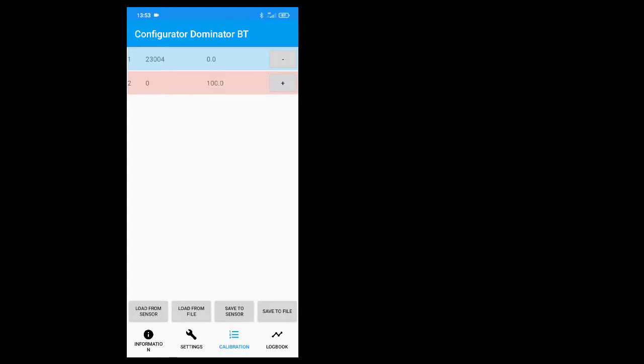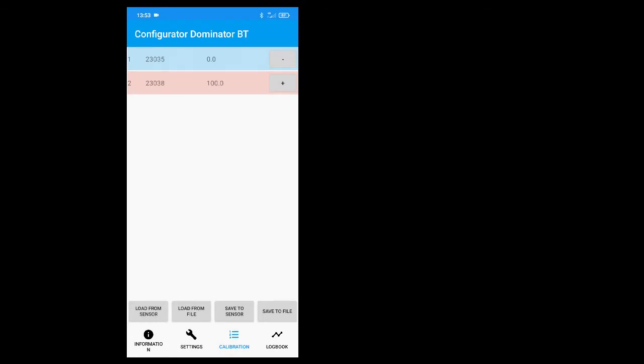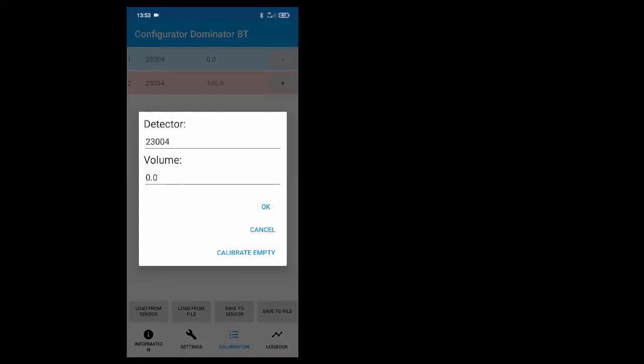Push the calibration button. The blue lines are already stored in the sensor and the red line is the current detector value at the given moment. The right column shows fuel level in percent — 0% is for an empty tank and 100% stands for a full tank. When the sensor is not filled with fuel, select the row with zero level and click Calibrate Empty, then save to sensor.